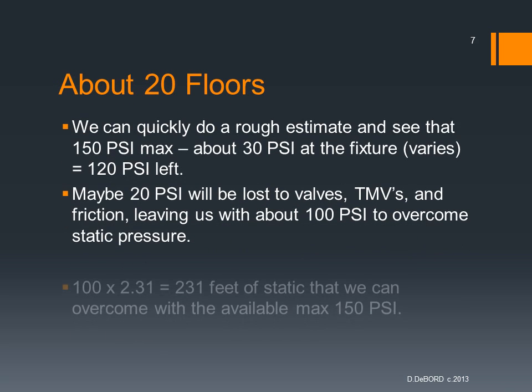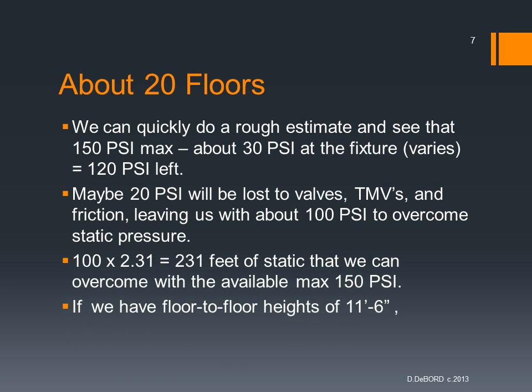We could do some quick calcs and do a rough estimate to see that 150 psi minus about 30 psi at the fixture. Of course, that varies. Some showers are 40 psi or more. And that leaves us with 120 psi. Maybe 20 psi will be lost through the valves, thermostatic mixing valves, and friction. And that leaves us with about 100 psi to overcome the static pressure. 100 psi, if we convert that to feet, that's 231 feet of static that we can overcome with that 100 psi, or our total of 150 psi.